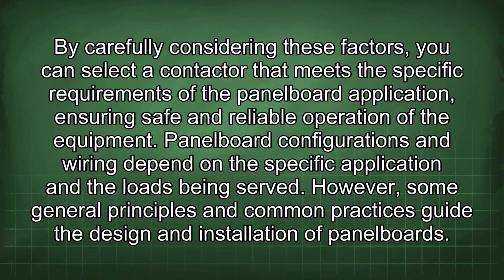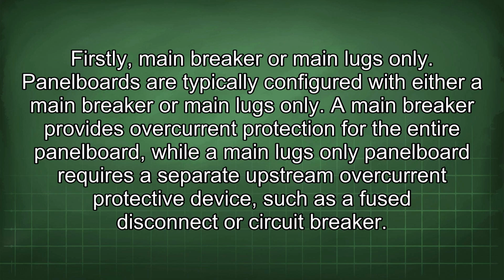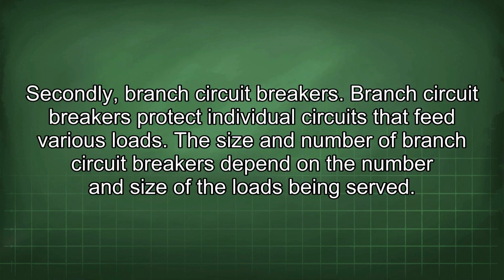Panelboard configurations and wiring depend on the specific application and the loads being served. However, some general principles and common practices guide the design and installation of panelboards. Firstly, main breaker or main lugs only. Panelboards are typically configured with either a main breaker or main lugs only. A main breaker provides overcurrent protection for the entire panelboard, while a main lugs only panelboard requires a separate upstream overcurrent protective device, such as a fused disconnect or circuit breaker. Secondly, branch circuit breakers. Branch circuit breakers protect individual circuits that feed various loads.